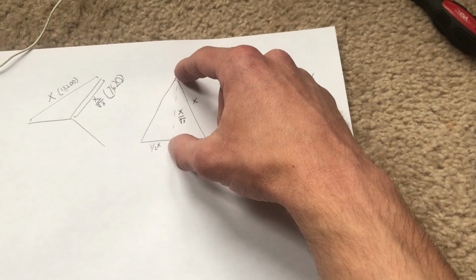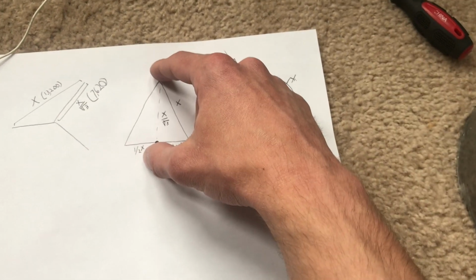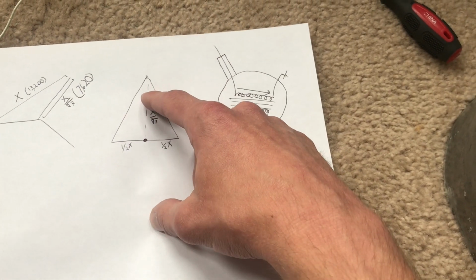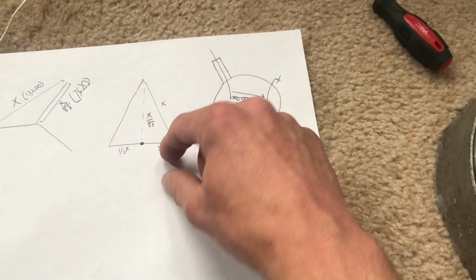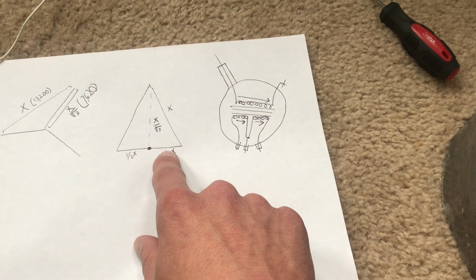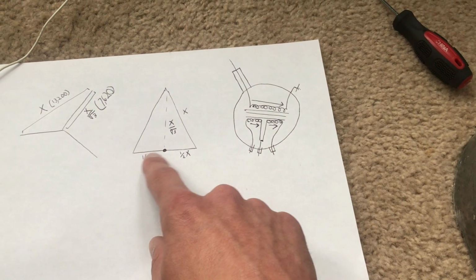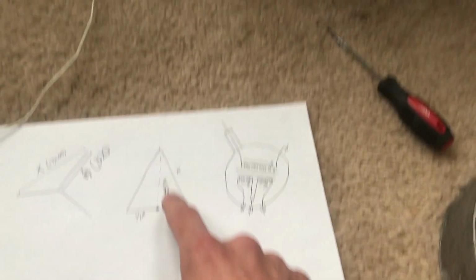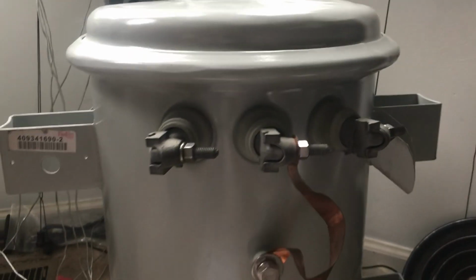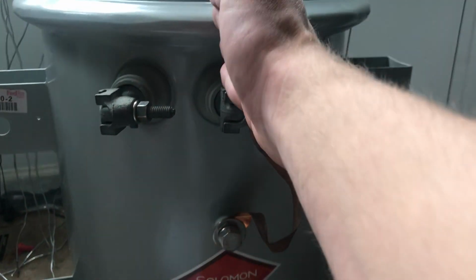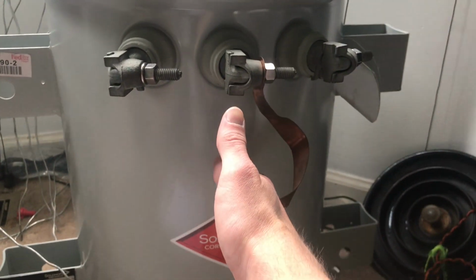My local utility company uses one transformer to get the third leg, which is the 208 from phase to ground, 1.73, again, constant. And then they have a larger single phase which feeds single phase loads. The bank, this would be the single phase transformer.